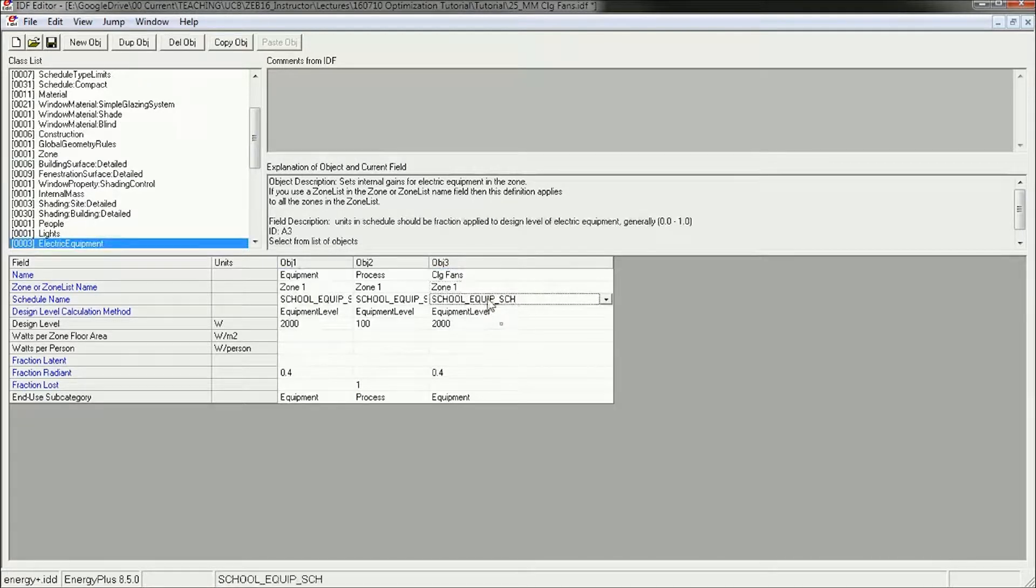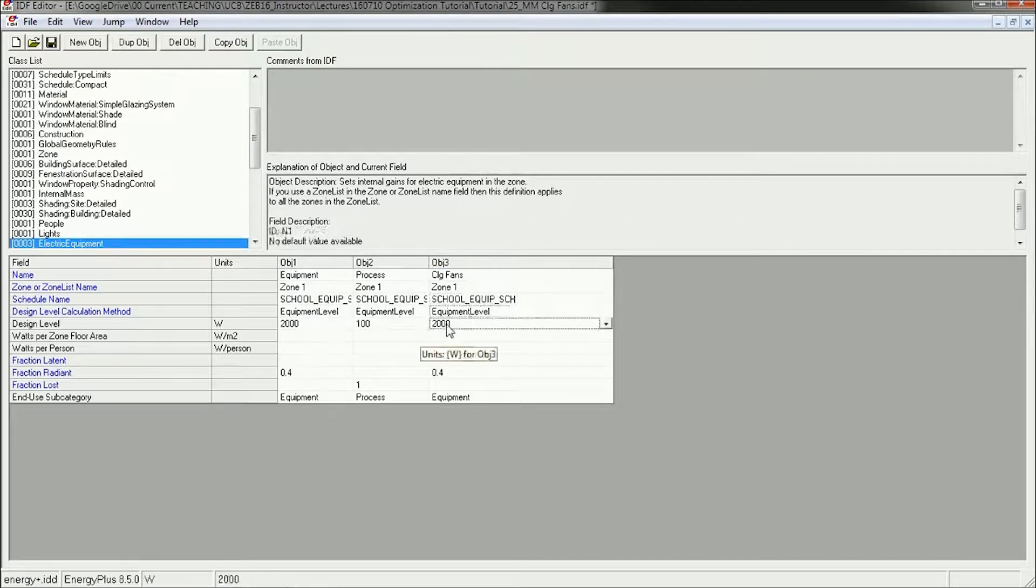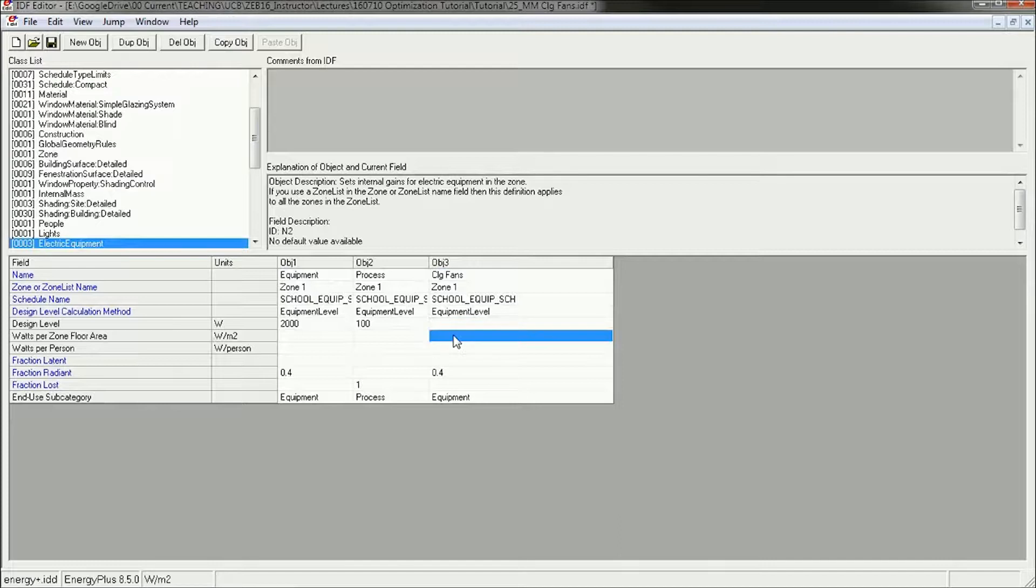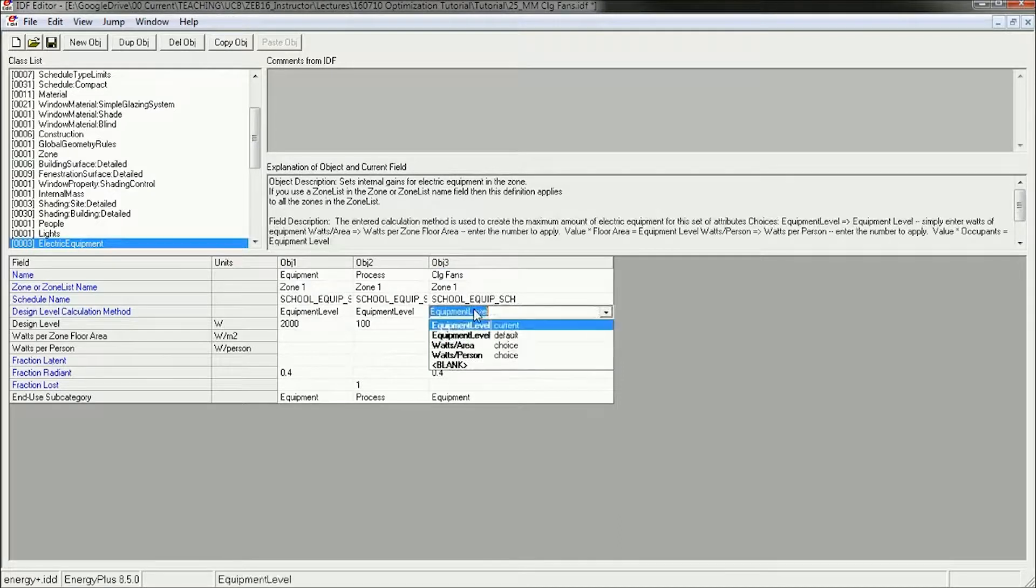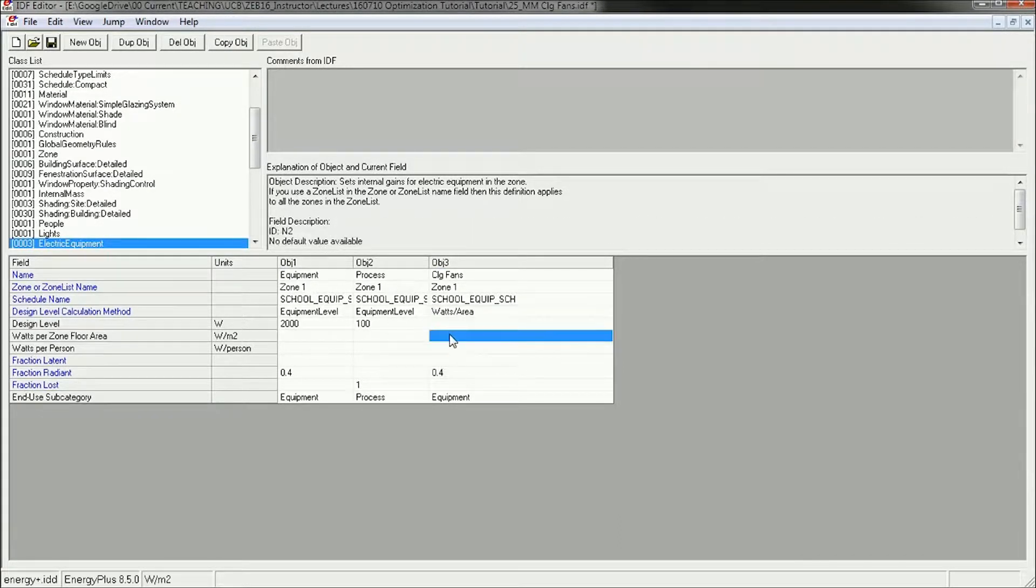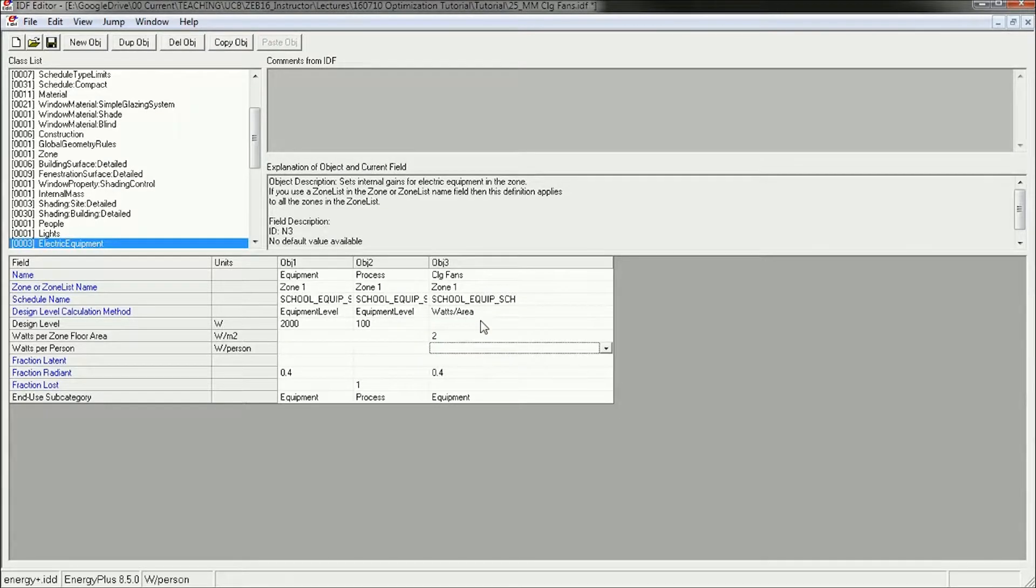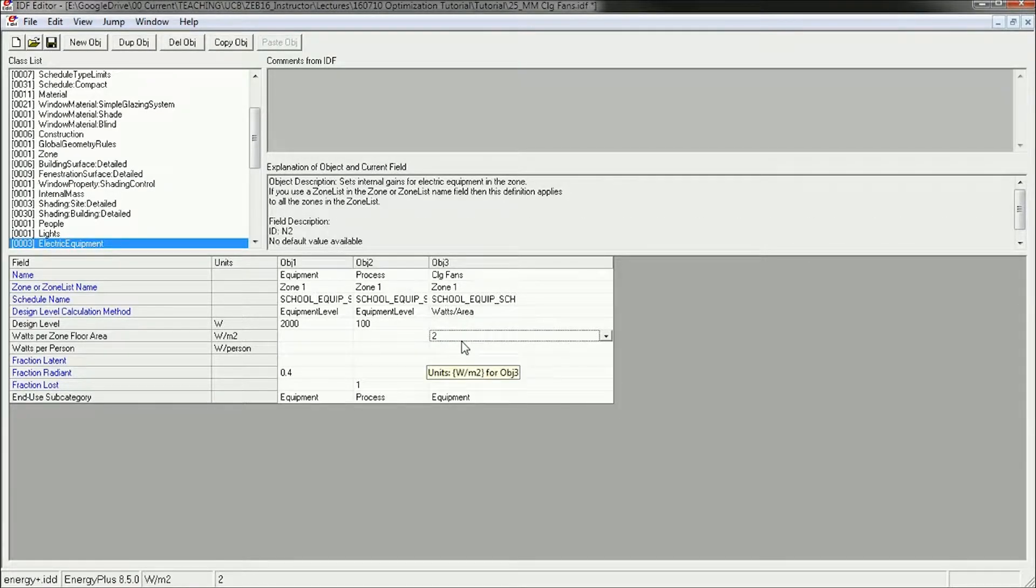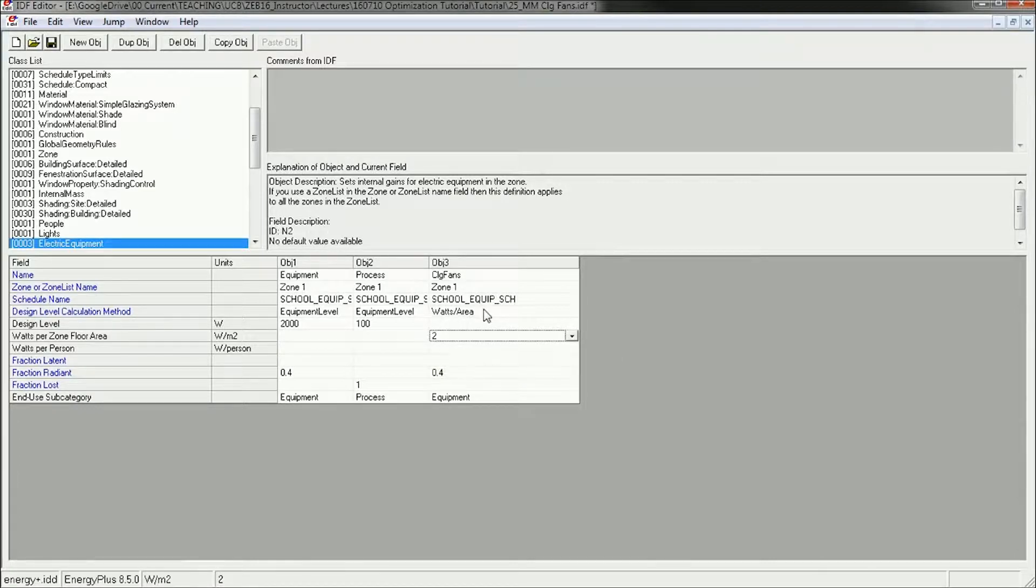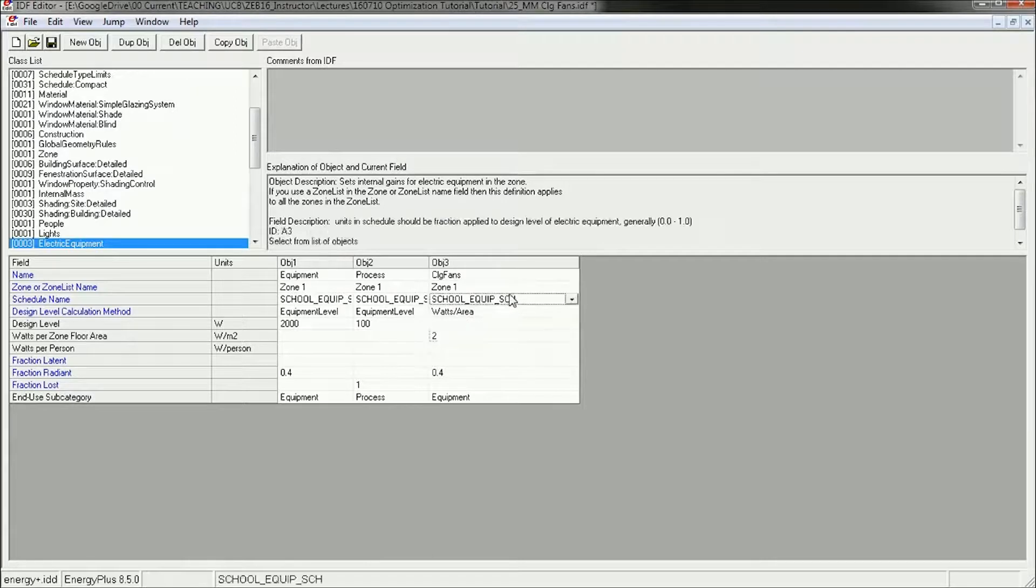We're going to want to make a new schedule for this, so we'll hold off on that. Instead of the design level, I'm going to use this as a watts per square meter. So I'm going to change this to watts per area. Let's use 2 watts per square meter for the ceiling fans. That's relatively typical for a high-efficiency ceiling fan. So we've got the power, now we need the time.